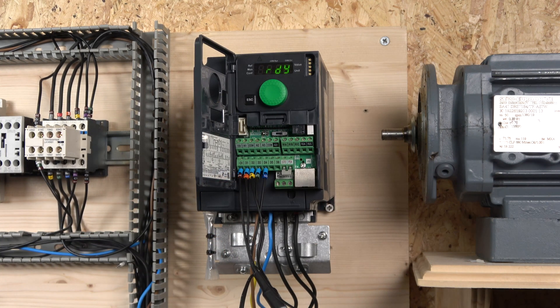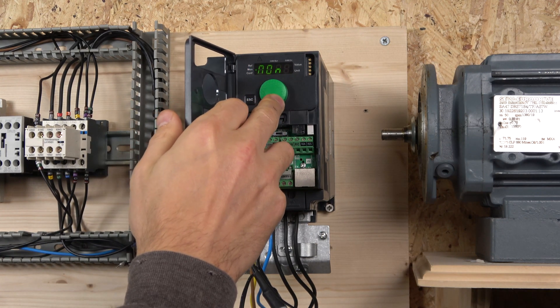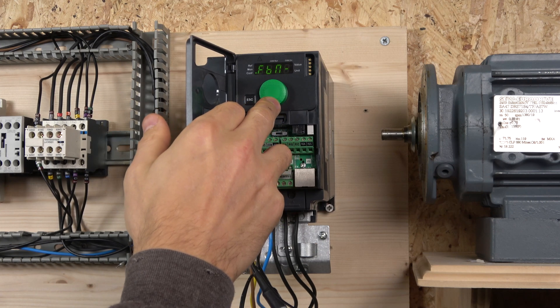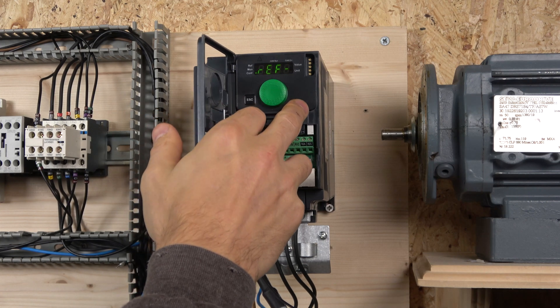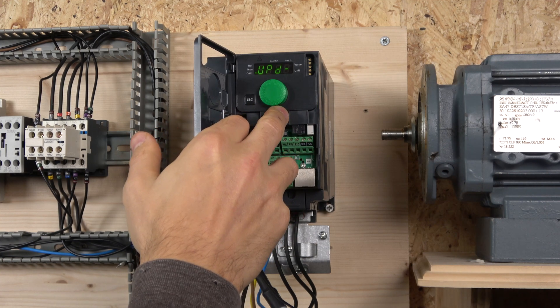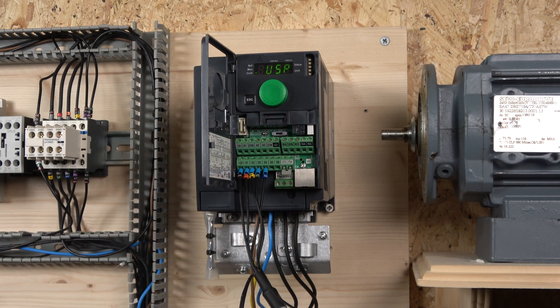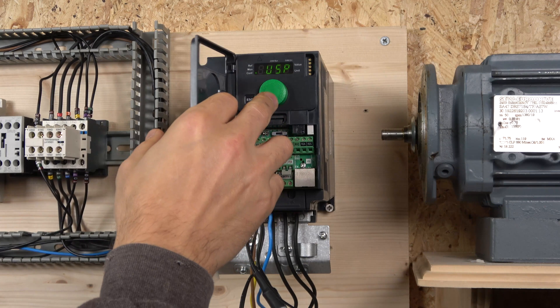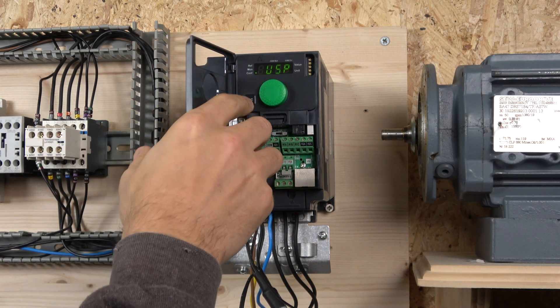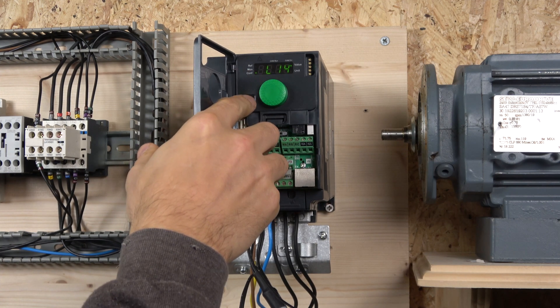To assign inputs, go to Functions — all assignments can be done in Functions. Go all the way to Functions, then go to the parameter called USP. In there, you can see the up assignment: I have assigned LI3 for up and LI4 for down.